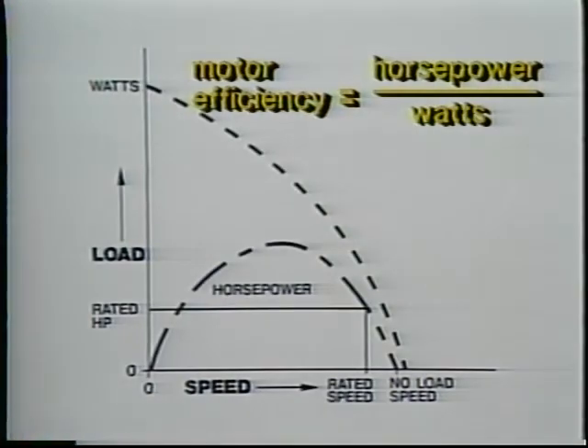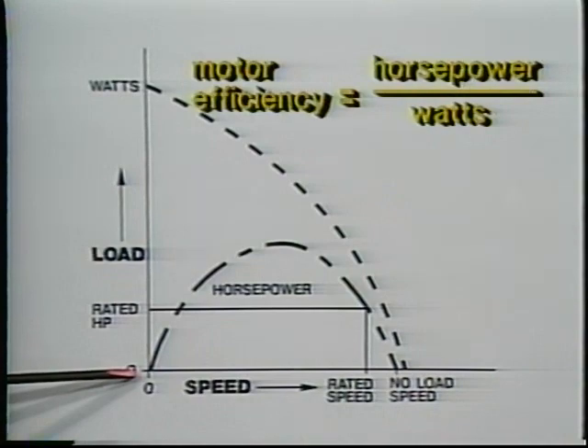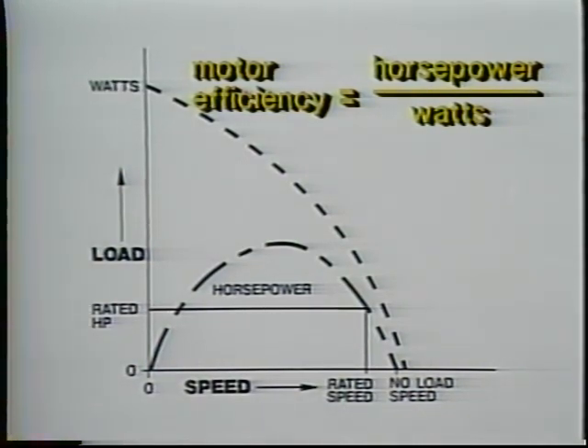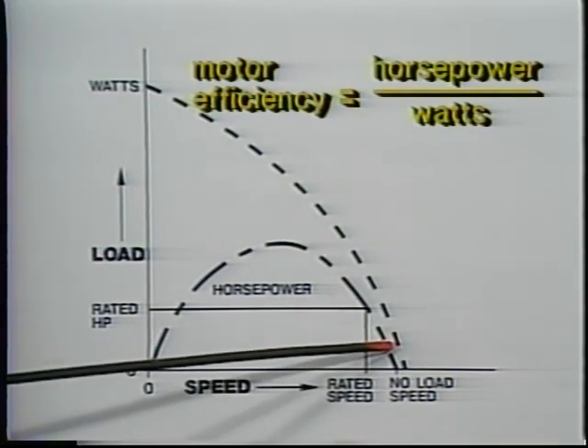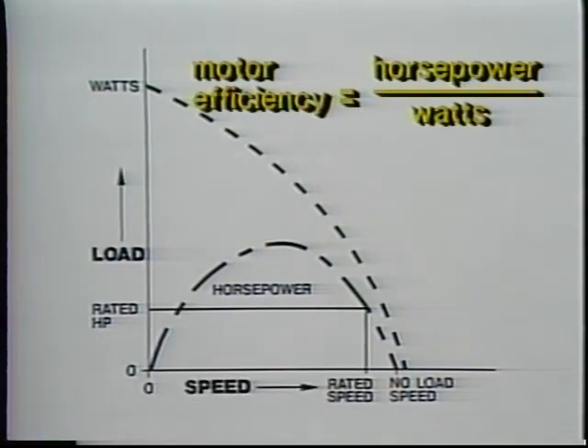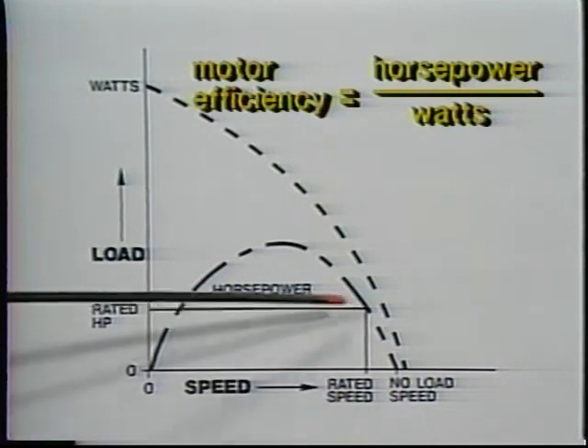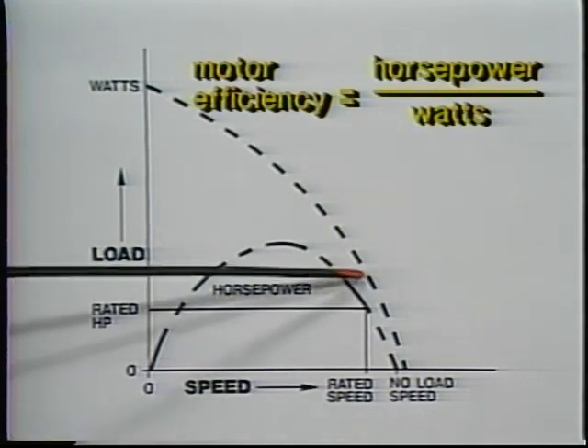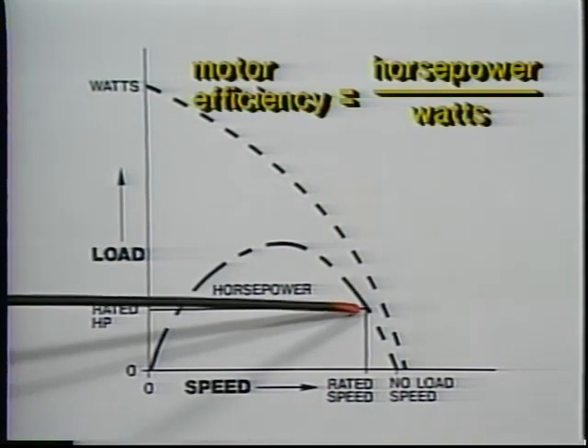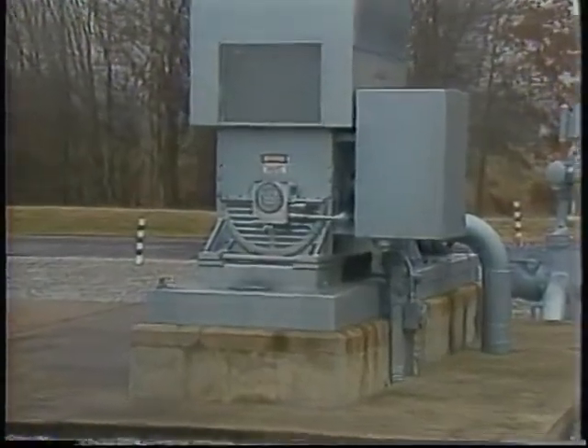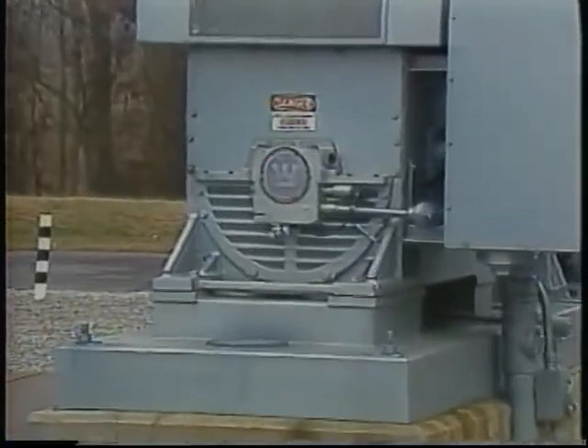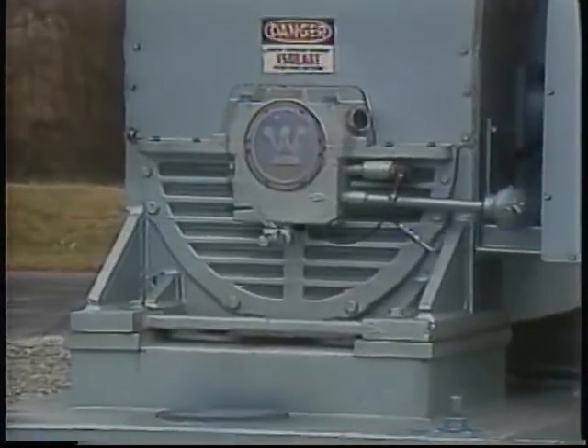We can see how the efficiency of a motor varies if we plot watts and horsepower together. At stall, the motor is producing no horsepower but watts input is very high because the motor is drawing a lot of current. At no-load speed, watts input is low but horsepower is zero again, so efficiency is zero. At rated power, a motor is consuming a lot of watts but also producing a lot of horsepower, so efficiency is quite good.